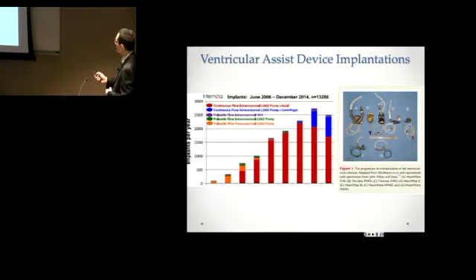Just a word for those people who are not very familiar with ventricular assist devices or what they're like. So this is a picture. They're surgically implanted. For the most part, they require sternotomy. There's an inflow cannula that goes into the left ventricular apex, so the blood will be sucked out of the left ventricular apex and go through this pump. The pump is continuous flow, so essentially there is a rotor here that rotates continuously. In this pump, it's about 10,000 revolutions a minute. Then it pumps the blood and connects somewhere to the ascending aorta. So it essentially bypasses the whole left ventricle.